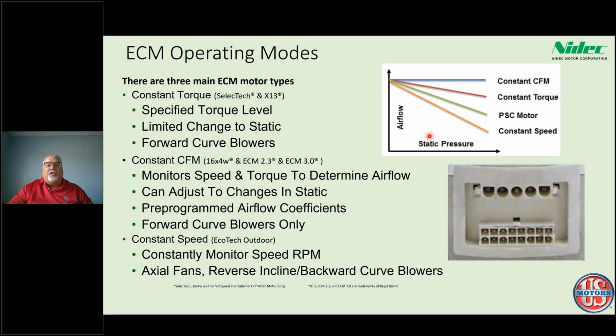So as static pressure increases with constant CFM, so will the motor speed, because it will be able to keep up with that change in static pressure. So as filters get clogged or dampers get closed and static pressure increases, you're going to get the same CFM with this, and it really will work itself to death in some cases. One of the ways this was originally sold was that it's going to solve all your bad ductwork problems, and obviously that hasn't been the case, but it does a good job. It really is a great motor, and we've made some improvements there as well.